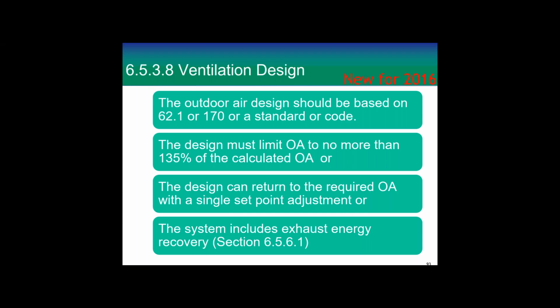So what this is about is, green buildings, and it was very popular for a while, has a thing where you get a point for putting more than 130% of the required outside air into the space or into the system. And this point was causing more energy to be used. So we'll let you do it, but if there's more energy used, or if you start having other problems, we want the control system to be able to go back to the required setting at just one, easily.